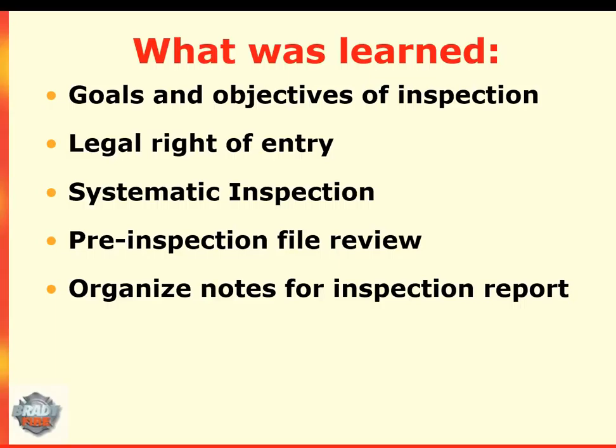Number 2, there are 4 ways to legally enter property to conduct a fire inspection. You should always present credentials and state the nature of your inspection request. Then you must have: 1, legal permission from the owner or legal resident; or 2, when an owner refuses entry, you must obtain an administrative search warrant based on probable cause to continue your inspection; or 3, an exigent circumstance permits warrantless entry to mitigate an emergency; and finally 4, areas that are open to the general public during public operating hours allow you to inspect those areas.